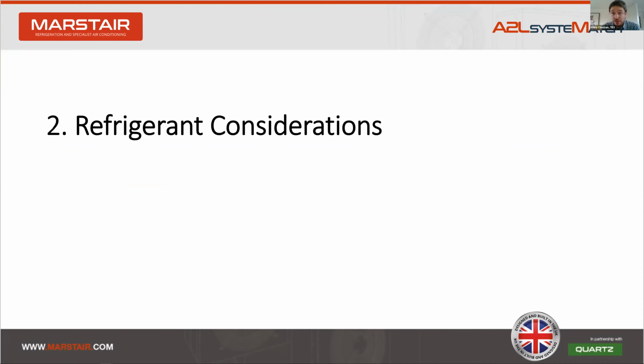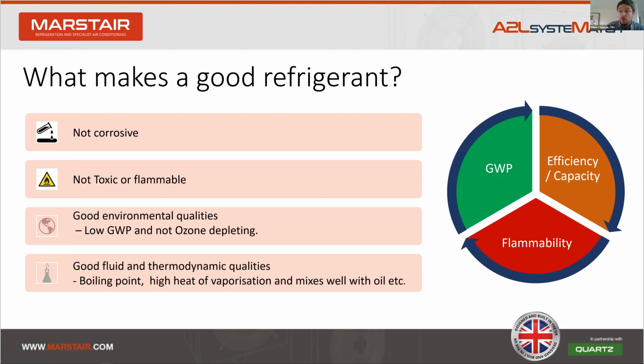Okay, so refrigerant considerations. So what makes a good refrigerant? Well, obviously it can't be corrosive, and also, preferably you don't want it toxic or as little flammability as possible. Good environmental properties in terms of low GWP and not ozone depleting, and good fluid and thermodynamics, so you get good capacity and energy efficiency. Unfortunately, there's a balance to be had. We have to make a compromise. For instance, if we have the option of using a refrigerant which is slightly flammable, then it gives us the potential for better efficiency.